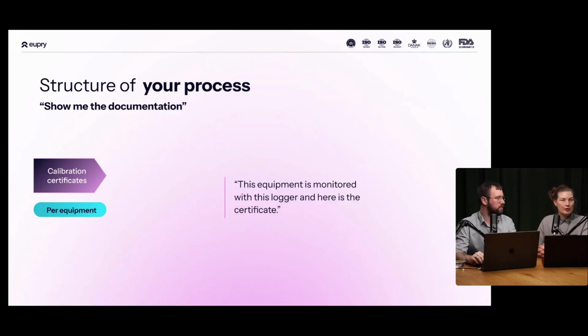So of course, you would show the documentation to answer this question. You'd show that this equipment is monitored with this logger, and here's a certificate. You're showing the certificate, and also showing that the requirements you listed are actually checked one-to-one. So if you have a requirement for a certain uncertainty to be calibrated at, you should be able to read that from your certificate. That also feeds into the fact that you need competent people who can read a calibration certificate to have good documentation. So there's both the documentation itself, and the review of the documentation, whether it's a mapping report or a calibration certificate.